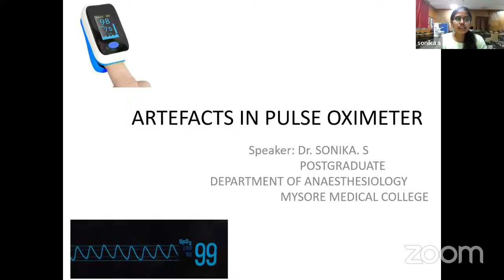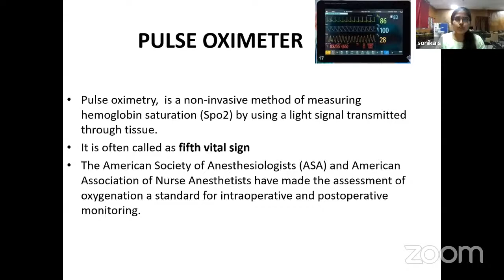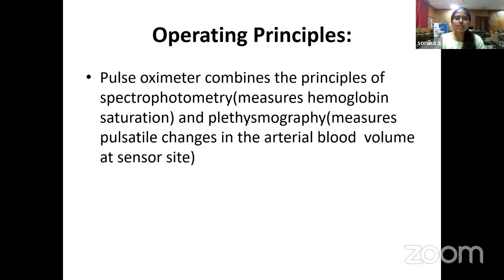The American Society of Anesthesiologists and the American Association of Nurse Anesthetists have made the assessment of oxygenation a standard for intraoperative and postoperative monitoring. In addition to measuring oxygen saturation, pulse oximeters with additional wavelengths are now available to measure carboxyhemoglobin and also methemoglobin. The operating principles: the pulse oximeter combines two principles, one is spectrophotometry, the other is plethysmography. Spectrophotometry measures the hemoglobin saturation, and plethysmography measures the pulsatile changes in the arterial blood volume at the sensor site.